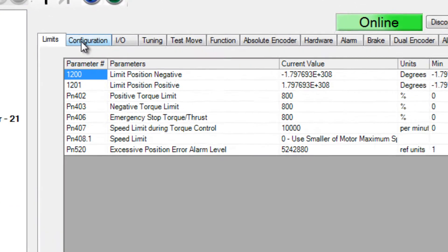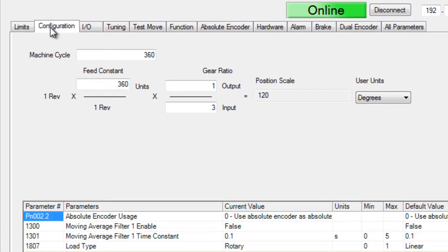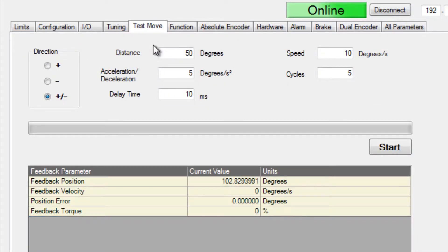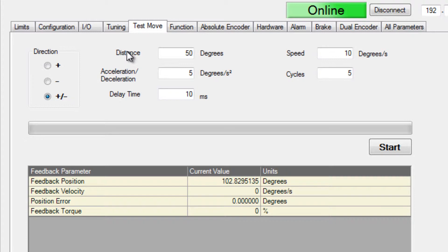In the configuration tab you can see it has been configured for degrees. Before using test move, make sure that the controller is not in run status, otherwise the program can retake control of the axis and the test move will not work.